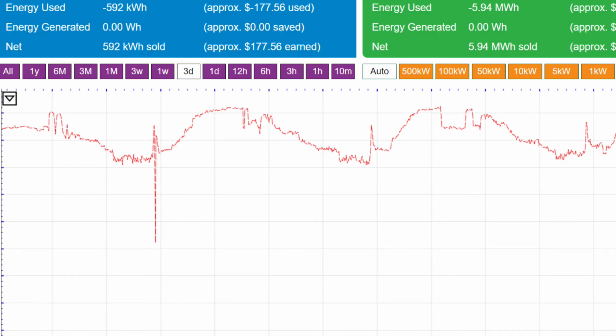What we've seen on the Matson unit, if we could go to that third screen showing three days of kW cycling. All right, what you're seeing there is a highly detailed three days of function. Let's look at that middle peak. You'll see a sharp downward spike that happens every day at around 5:30 in the morning. If you go to the following peak, you'll see another spike, and then the third spike in the next hill. You see three valleys and three spikes.